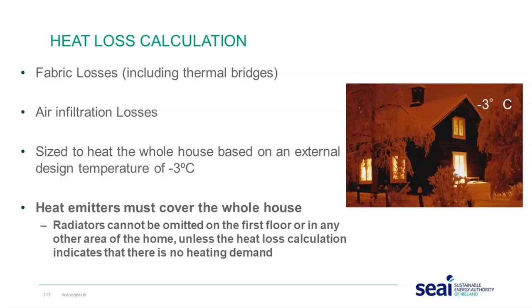So we can't just fit radiators downstairs and hope that the heat goes upstairs. We need to ensure that all rooms are heated by radiators, underfloor heating, or by whatever means, unless we can demonstrate through calculations that there's no requirement for heat in the room.